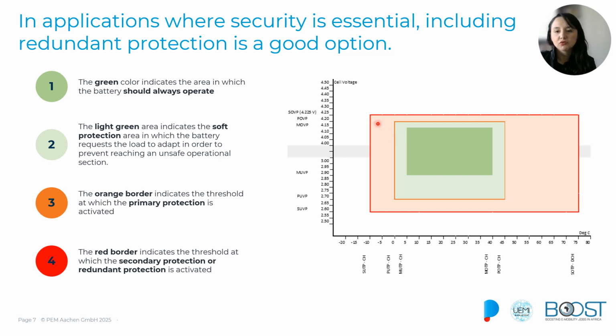In that case, the red protection is secondary, usually under normal operations. We should never reach that point, but if any of the measurements or the contactors or the BMS fails, that second layer will ensure that the system is still protected.